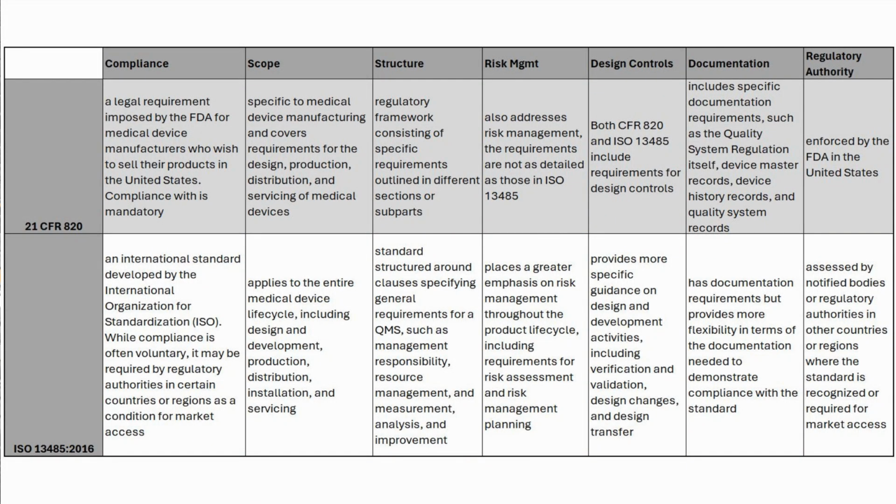Another area that I think is key to bring up too is the specific requirements around the design development activities. So although it is again in CFR 820, 13485 is bringing a bigger emphasis in regards to design controls specific to V&V and design changes along with the design transfer.